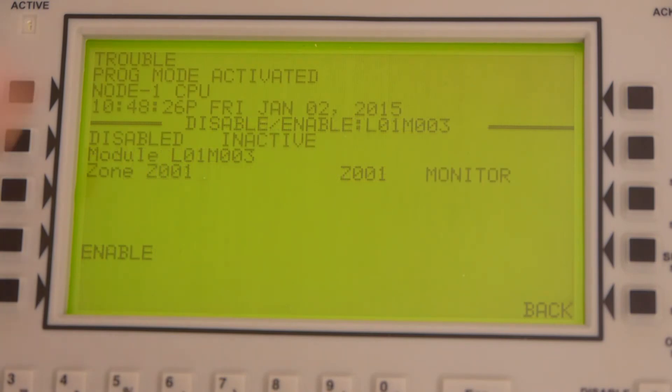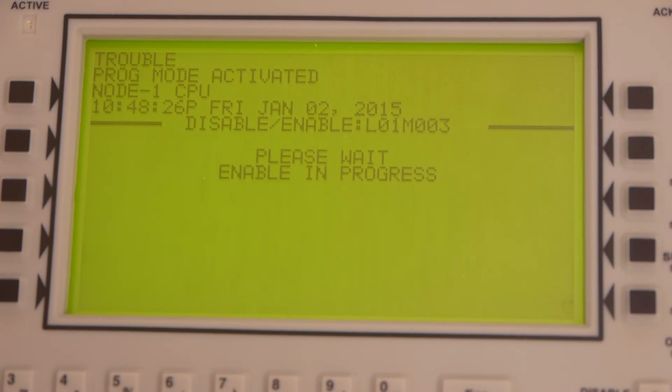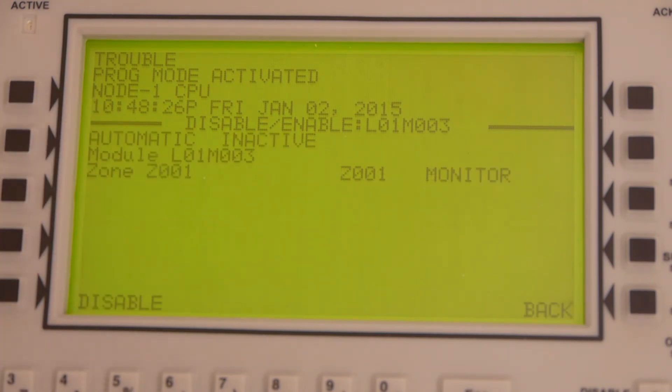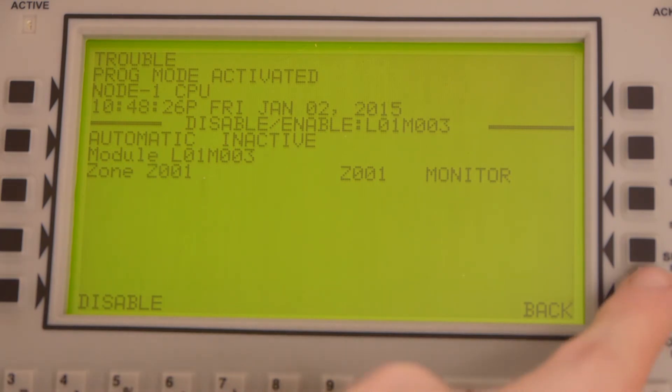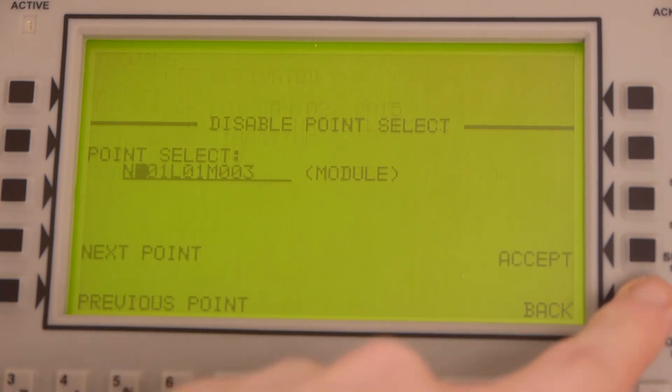You will see the same screen, but instead of disable, you're obviously going to press enable. You're going to want to make sure the device is not in alarm, because the panel will go into alarm if the device is in alarm when it re-enables. But luckily, ours is not.